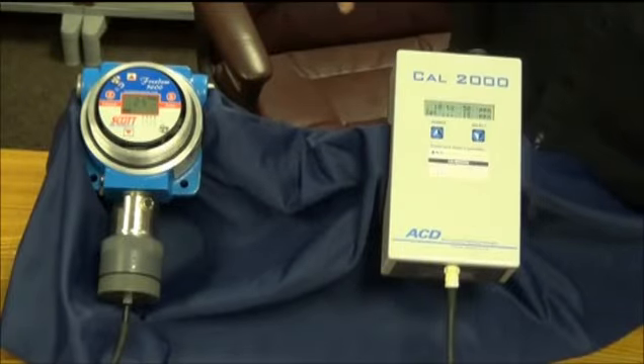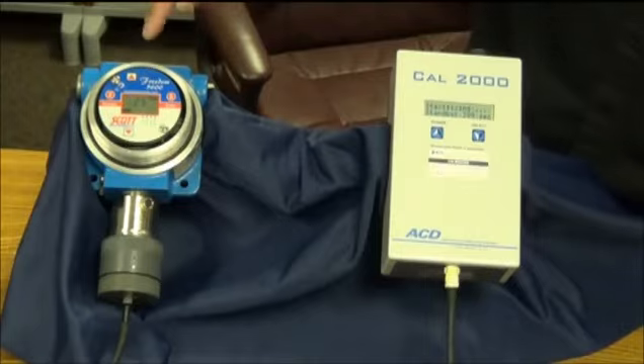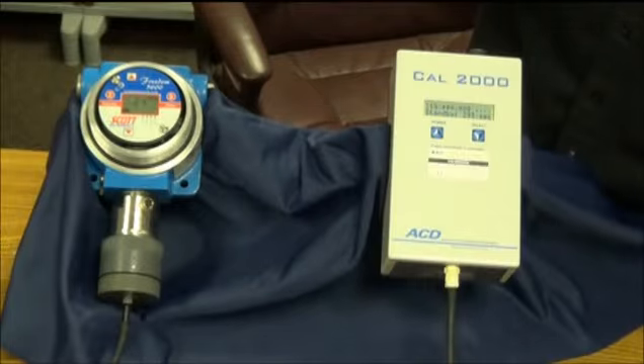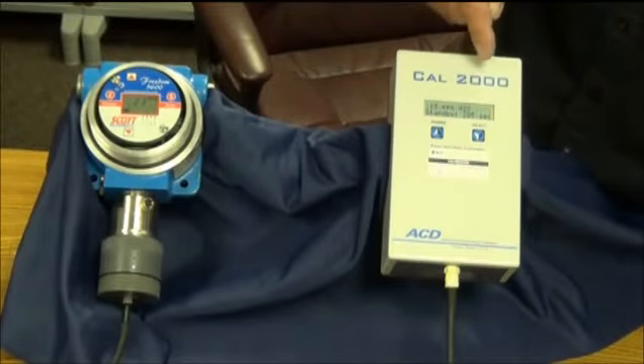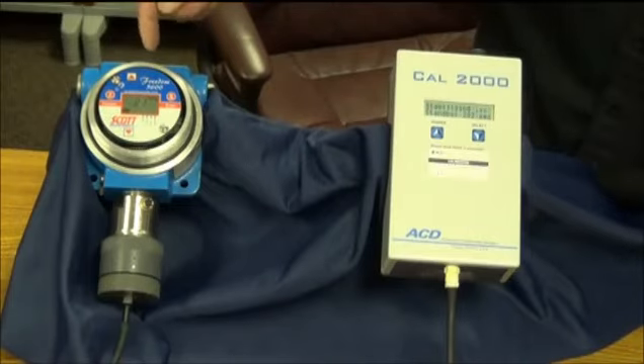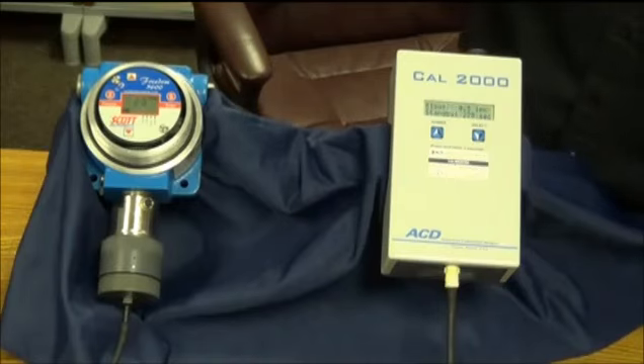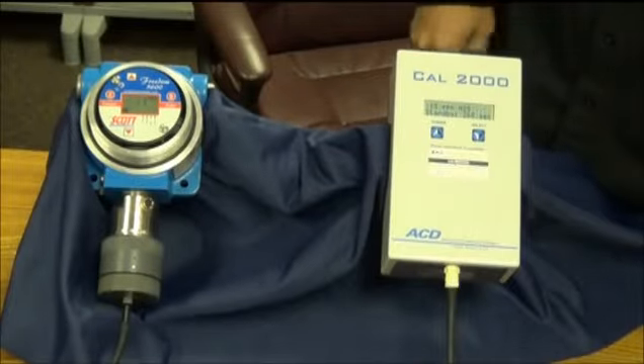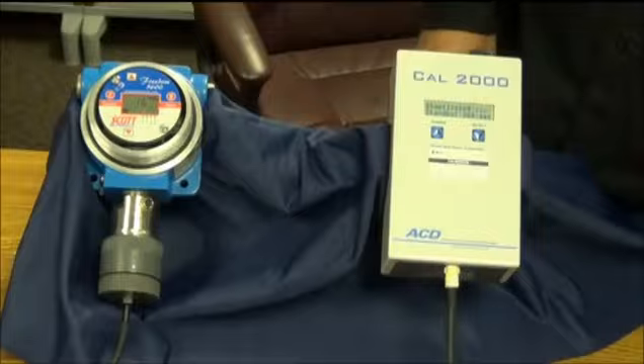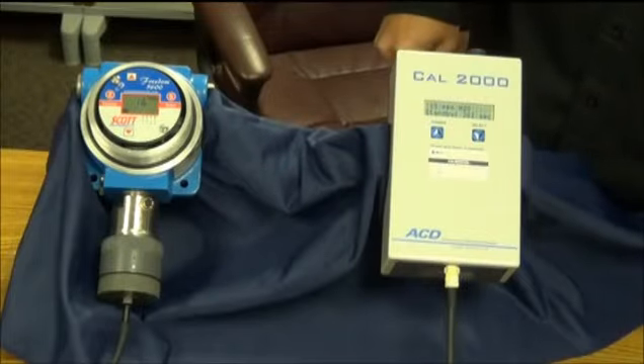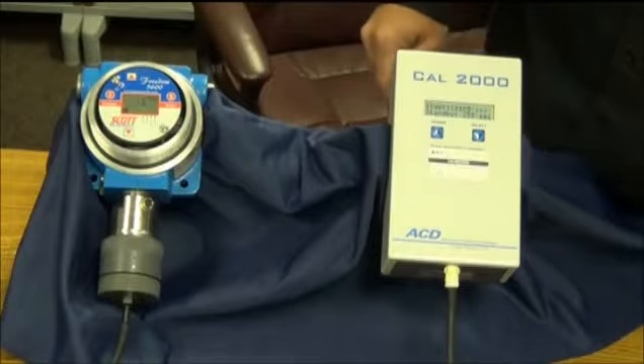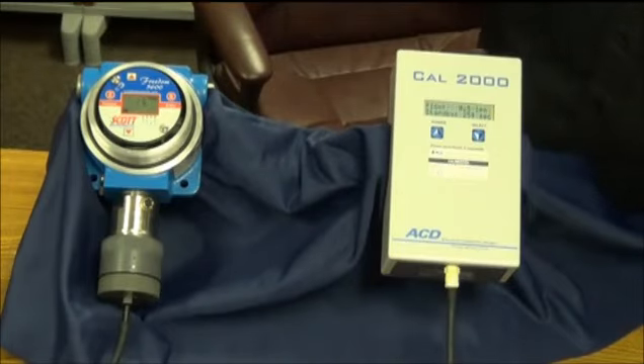Now the Cal 2000 starts its 5-minute countdown, but you'll see by the output of this Scott sensor how quickly it changes. The point of this is to show you that if you have some other kind of sensor that requires a specific output, you just set the output of the Cal 2000 to that output. In this case now I've changed it to 15. You see the Scott sensor dropping down. Now it's going to go to 15. So if you have several different brands or models of gas detector, you can use one calibrator, calibrate that sensor, and you've got your all-in-one here. You see it's dropping down, 17, 16, 15 is where we would calibrate this, and there it is now, and you're ready to go.